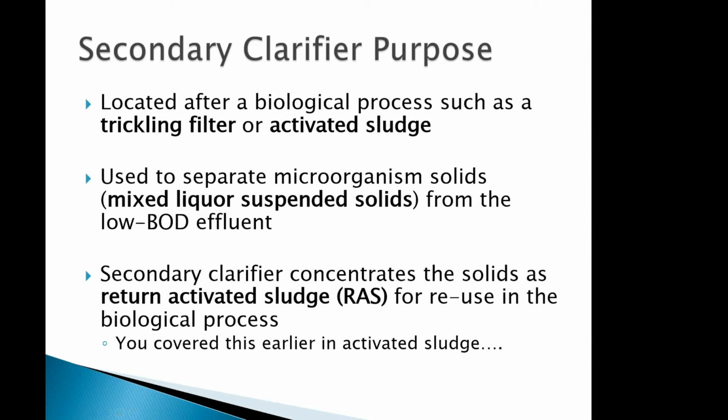Looking at secondary clarifiers, they operate very similarly to primary clarifiers, but they are generally located after a biological process. So those biological processes, such as activated sludge that Monte just talked through for the last hour, or even a trickling filter, these processes are converting your soluble or dissolved BOD into a solid form. Basically, the bacteria is growing while it consumes the dissolved BOD. And so we need a physical process to separate that material from the wastewater flow. And so we do that with a secondary clarifier.